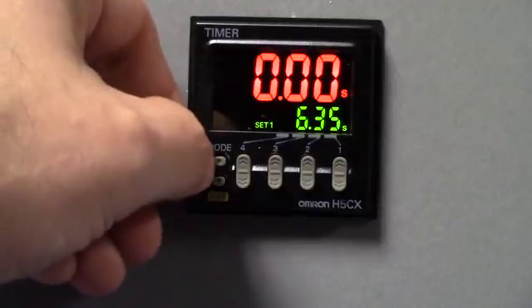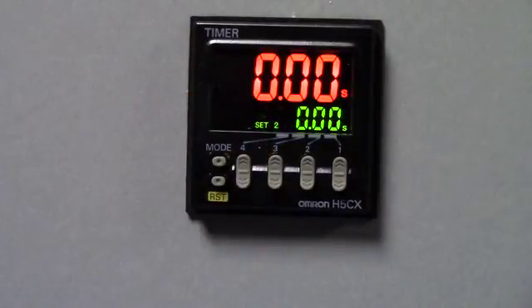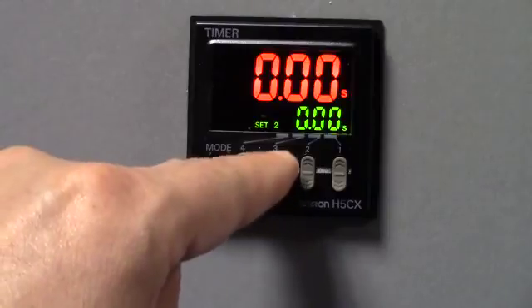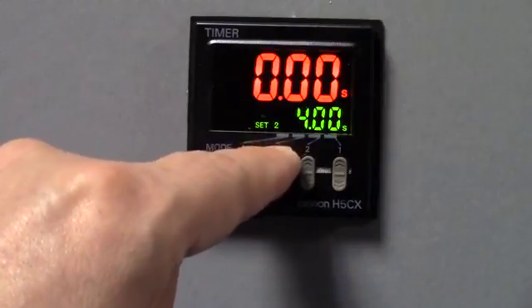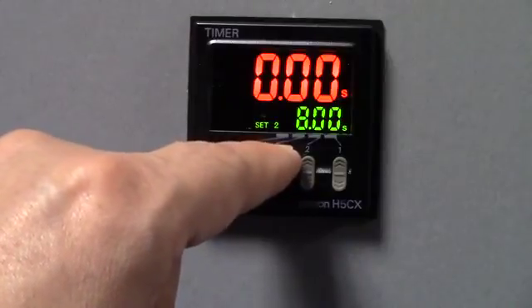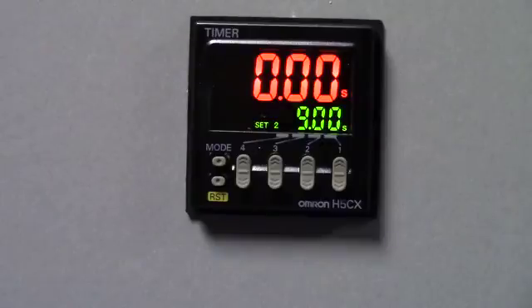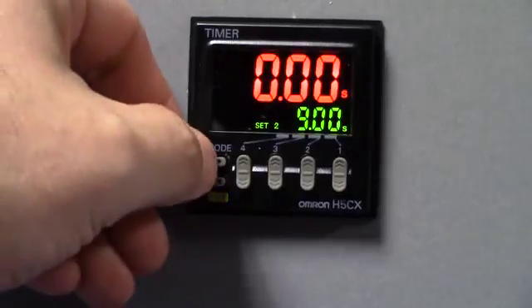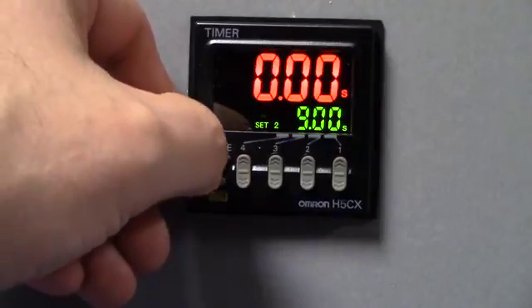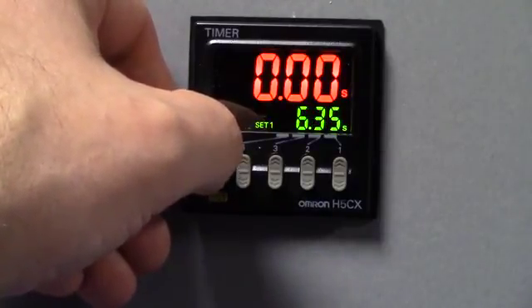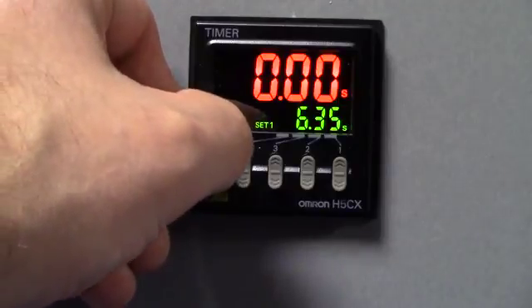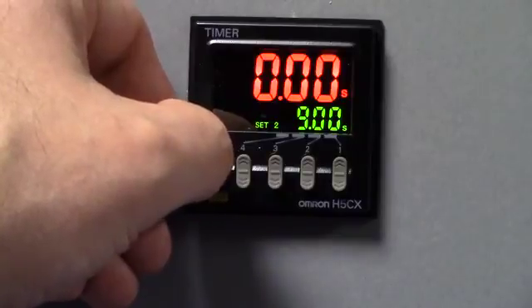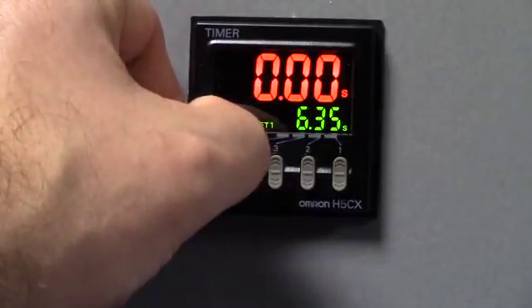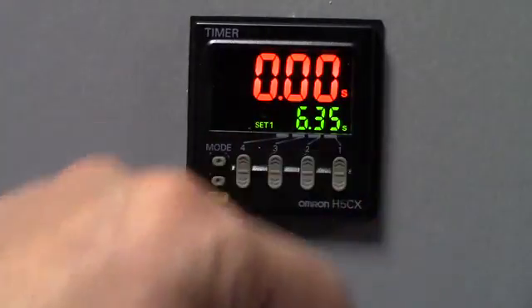I'm going to press the mode key, and now this is going to allow us to set the on time. So I'm going to keep it double zeros, and I'm going to keep it for 9.00 seconds. I'm going to press the mode key one more time. So there's our off time, set at 6.35 seconds. There's our on time. I'm going to press and hold the mode key for 3 seconds. As you can see, when you press and hold the mode key for 3 seconds, we're set.